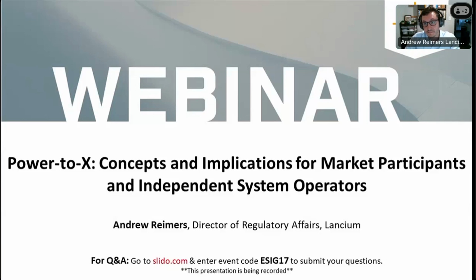But the more you can get these units actually participating in the SCED and be dispatched every five minutes, the better—units that can follow base points and don't inherently have big swings in their load, that's a solution. I just see several types of load, whether it's certain kinds of data centers, steel, or various thermochemical processes, that might not be able to behave that way. It really depends on the characteristics of the loads.